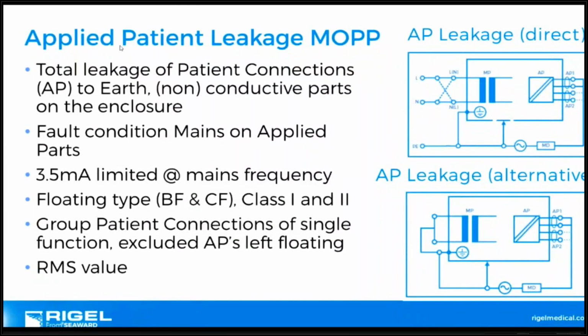Then we have applied patient leakage or means of patient protection, AP leakage direct and AP leakage alternative. Direct gets powered, so we're powering the device here, but this is getting the functional current. Alternative isn't, because we're shorting these together, but we are putting the mains and applied part here and here between these contacts, the protective earth and the applied part. So it's fundamentally the same as a mains on applied part fault condition as per 60601.